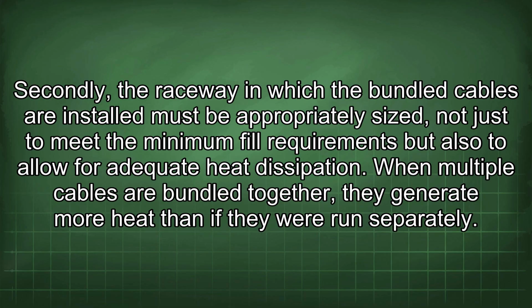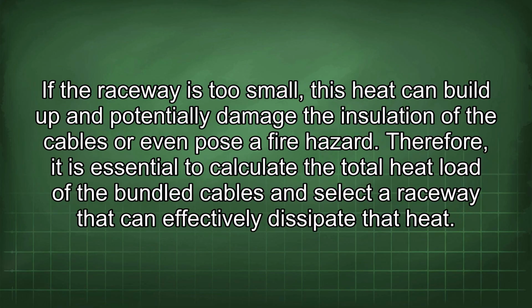Secondly, the raceway in which the bundled cables are installed must be appropriately sized, not just to meet the minimum fill requirements, but also to allow for adequate heat dissipation. When multiple cables are bundled together, they generate more heat than if they were run separately. If the raceway is too small, this heat can build up and potentially damage the insulation of the cables or even pose a fire hazard.